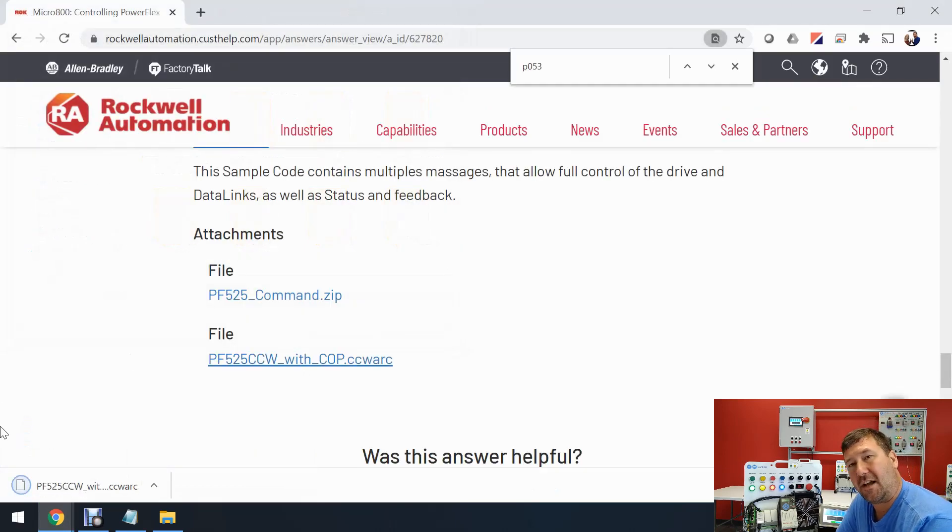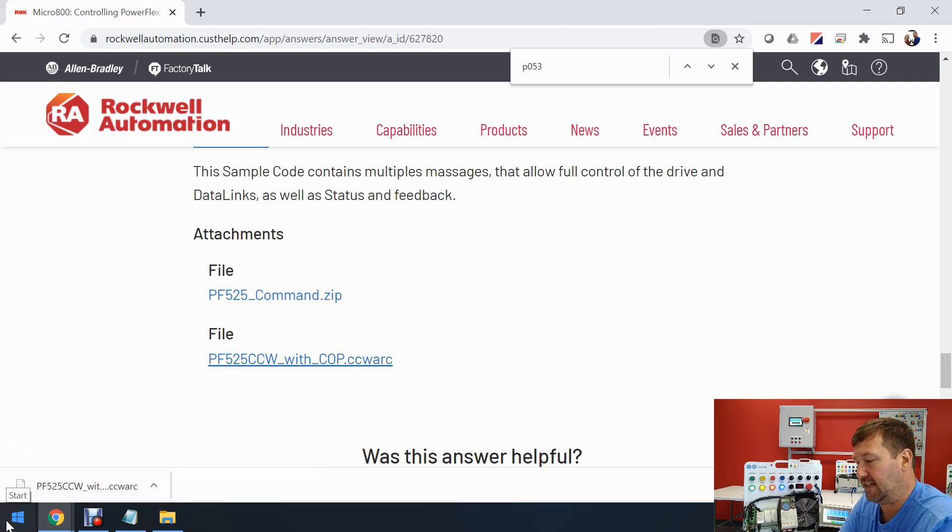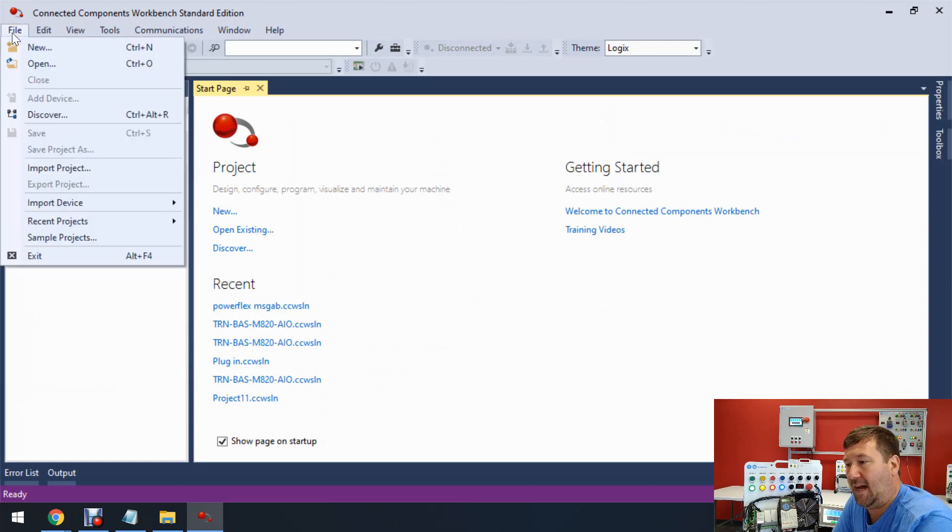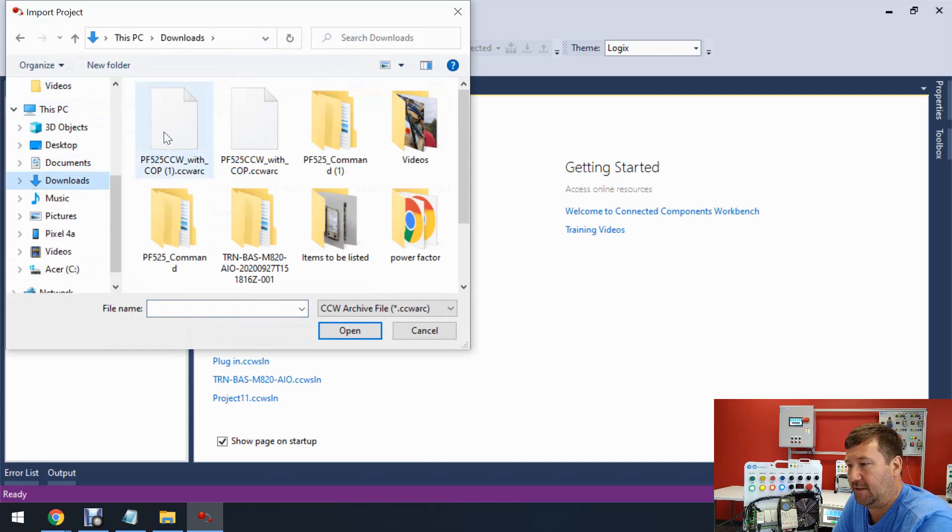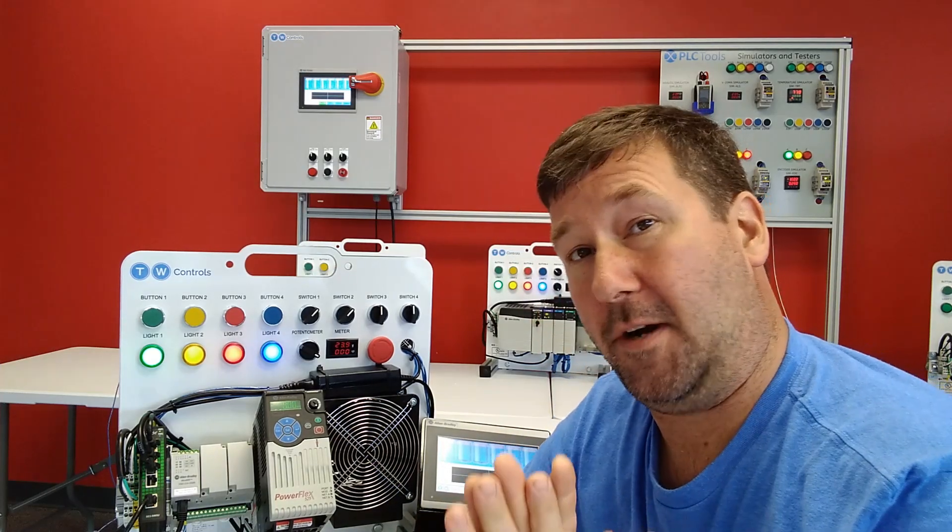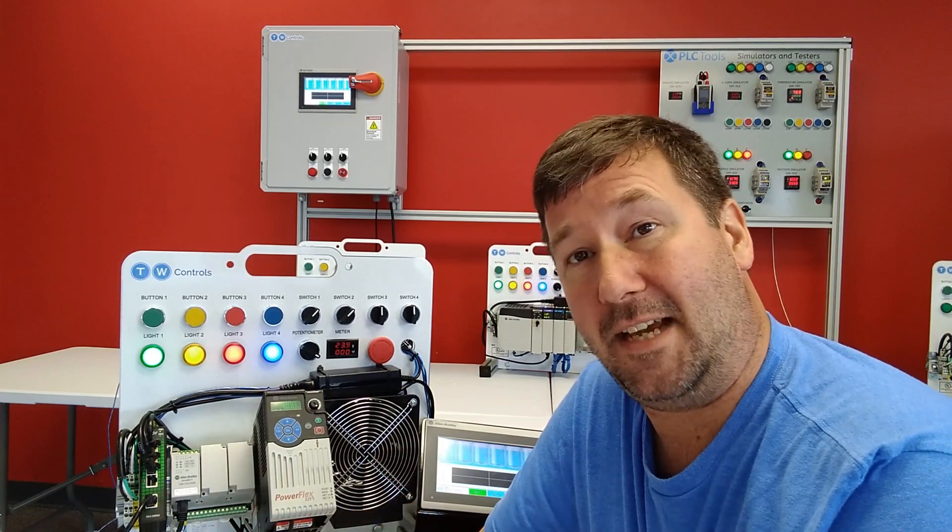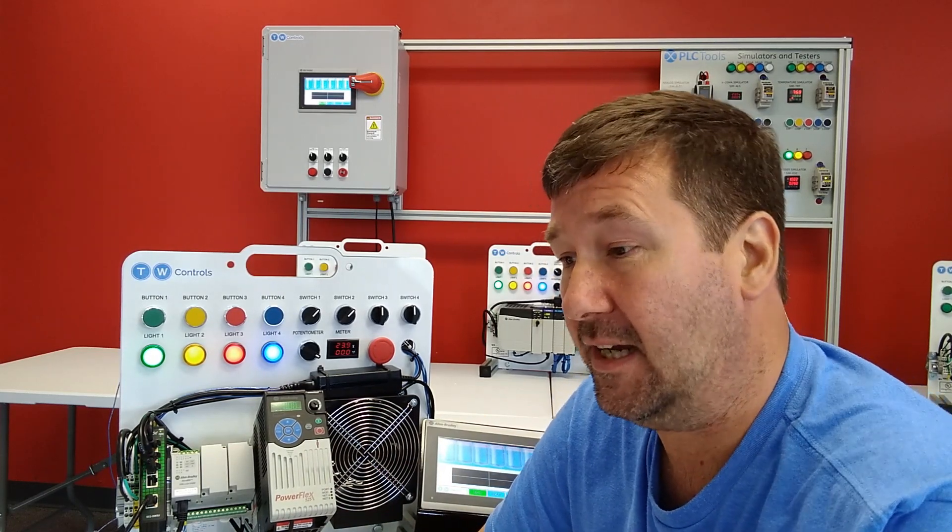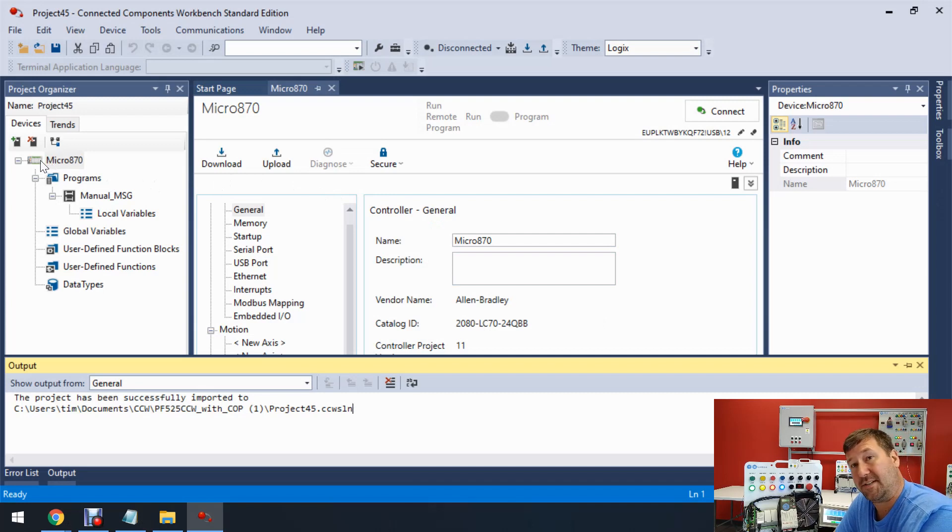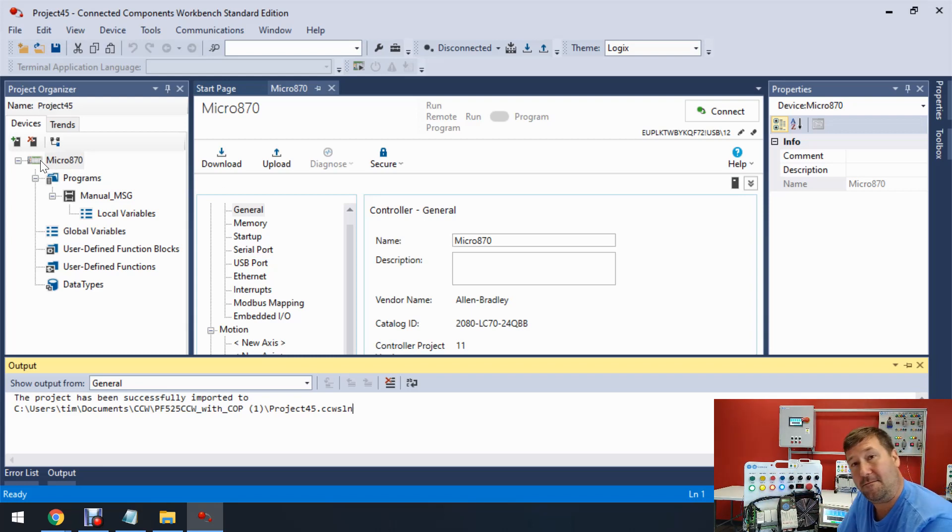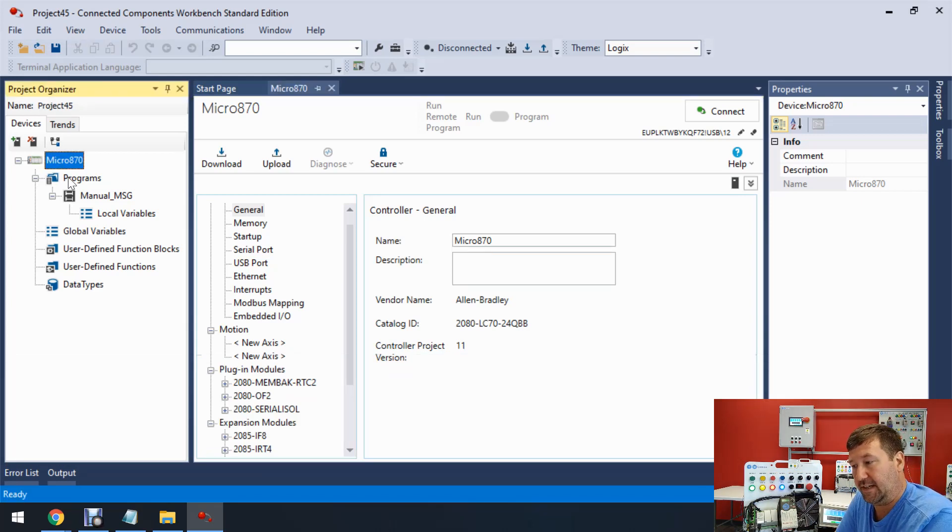And you're not going to be able to open this right out of downloads. You're going to need to open up your Connected Components Workbench software. And then you're going to go to file and import. And then go and find that file that we just downloaded. And then pause for a second because you're probably thinking, let's download this. Well, this is a sample code, but Rockwell may not have been using the PLC that you have in front of you when they made it. So let's go to the top of this tree that's labeled Micro 870, which is probably the first big red flag. And we may need to make a few modifications to make it fit for our Micro 820.